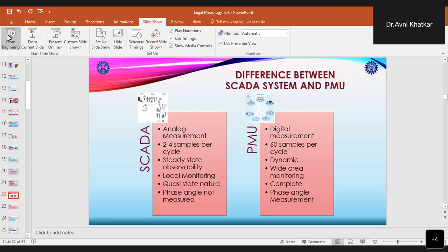However, if we have a PMU-based system, a PMU can continuously stream data with an absolute timestamp at a very high rate, for example, 25, 50, 100, or even 200 frames per second. And with this faster speed, which is over 100 times faster than a traditional SCADA system, we can measure the dynamic nature of the grid. And this streaming data, which is collected from multiple PMUs, can be used to develop customized, sophisticated algorithms, which can further allow the load dispatch computers to completely and continuously monitor the grid at the regional level and automatically perform the tasks of islanding, load shedding, and disconnecting the zones which can cause any disruptions and potentially threaten the stability of the grid.